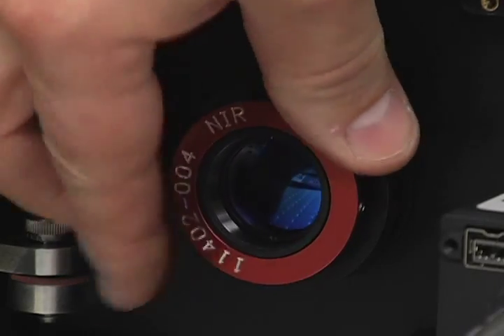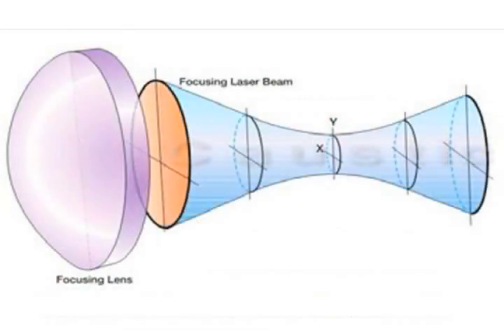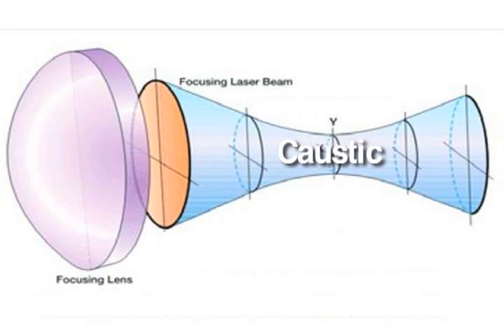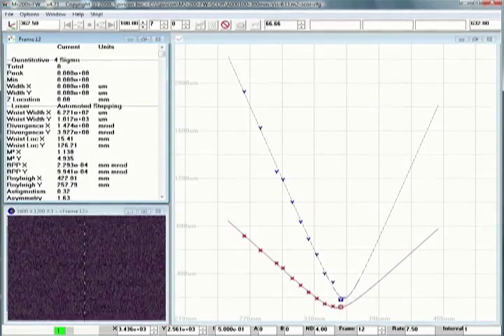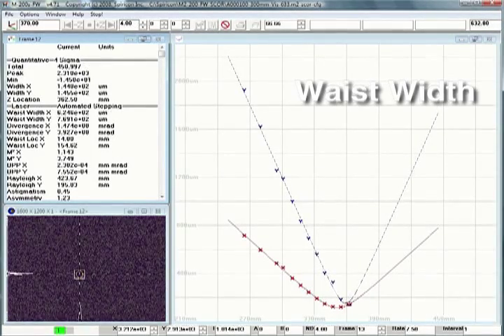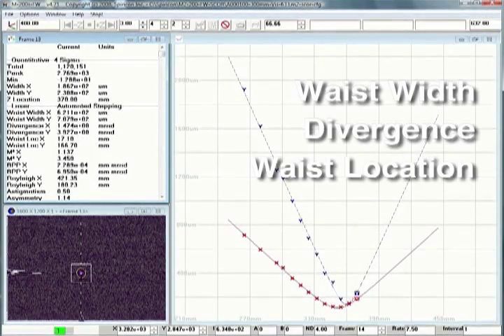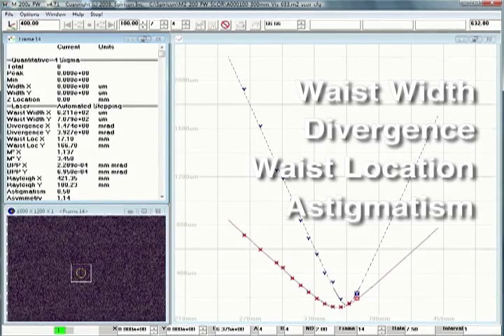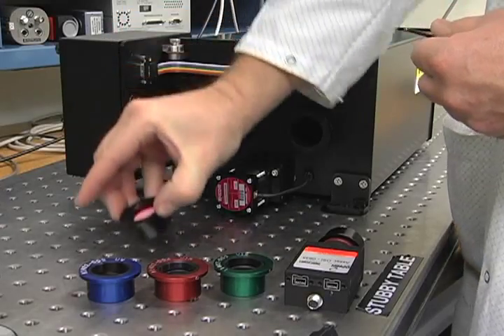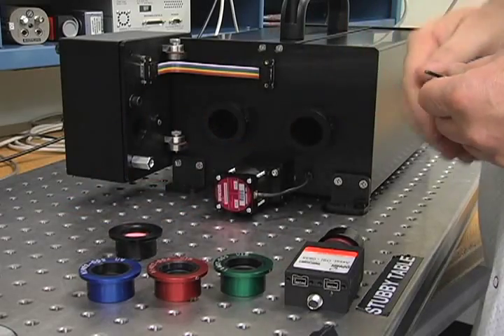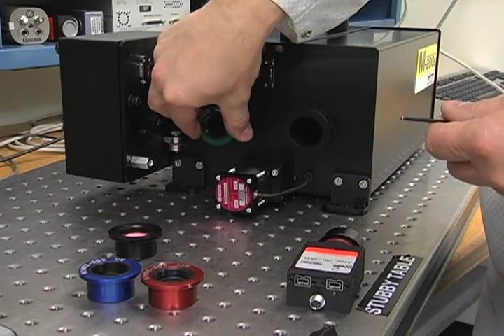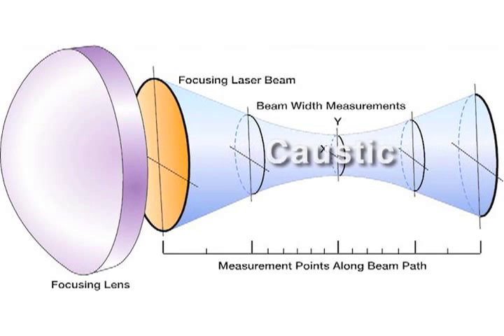To solve this problem and other measurement difficulties, a lens is used to create an artificial caustic that preserves the M-squared properties of the input beam and allows calculations of the original beam's waist width, divergence, waist location, and such things as astigmatism and Rayleigh length. A lens with known optical properties is used to create a beam waist in the focused region or caustic where these measurements are performed.